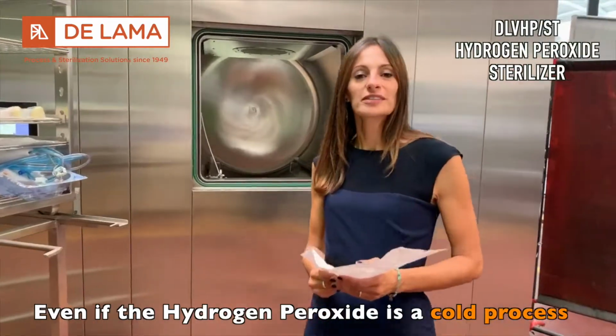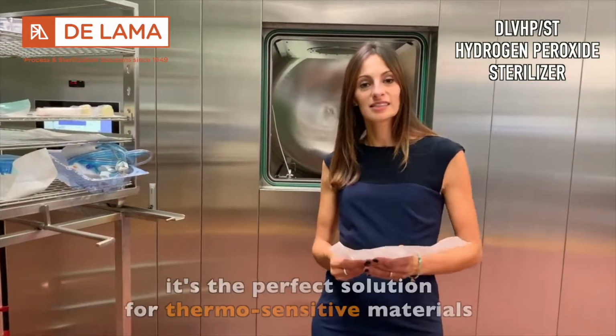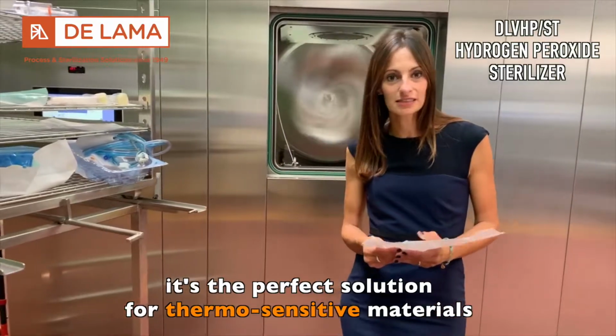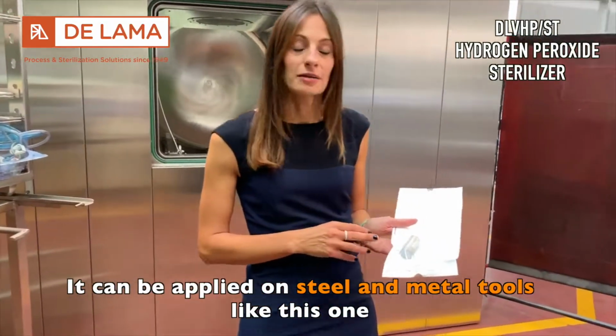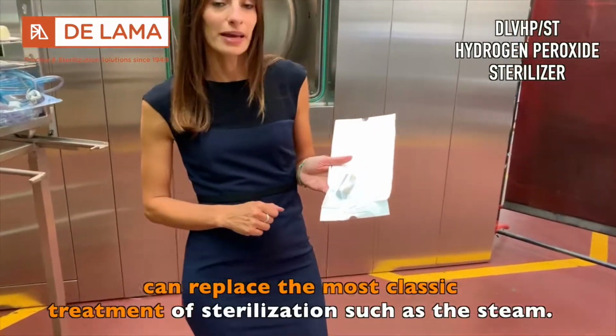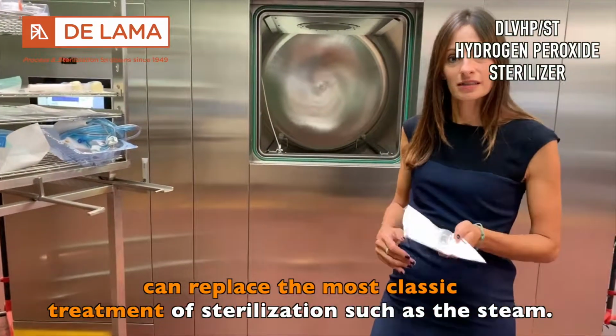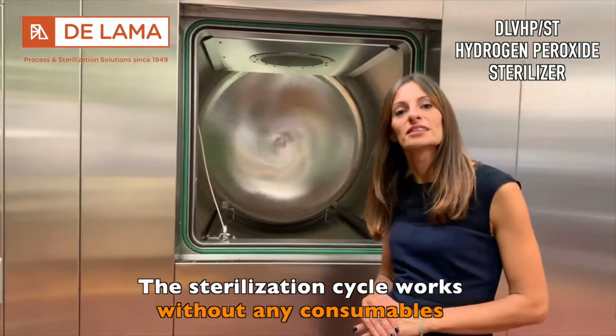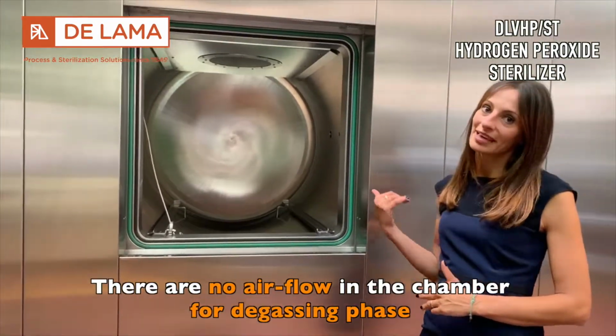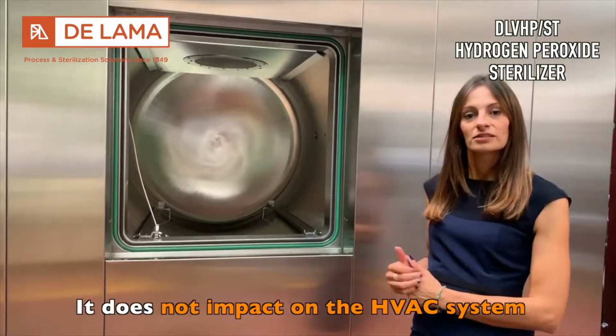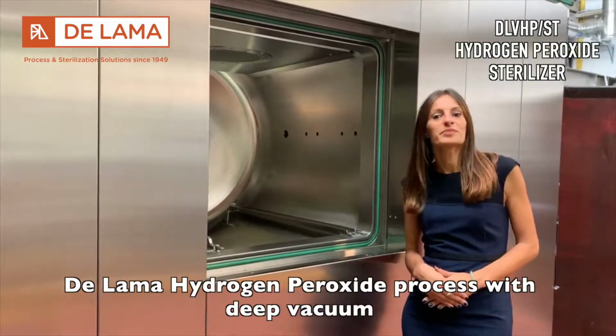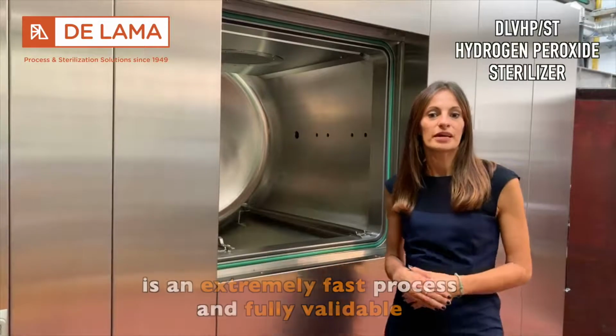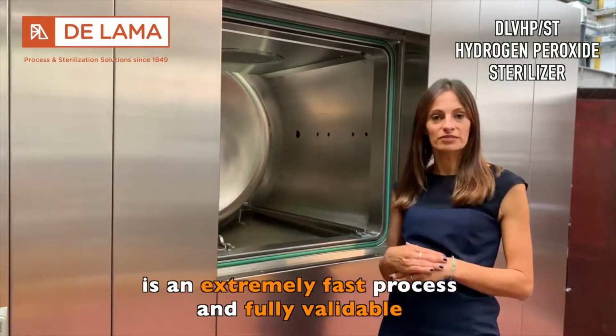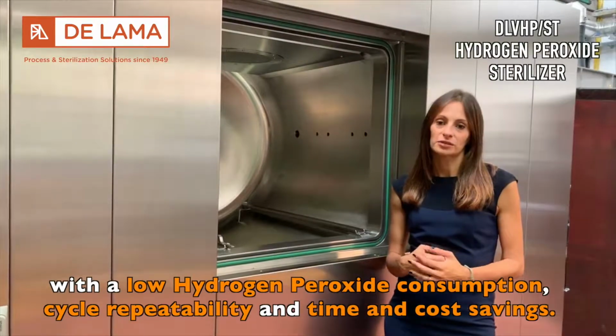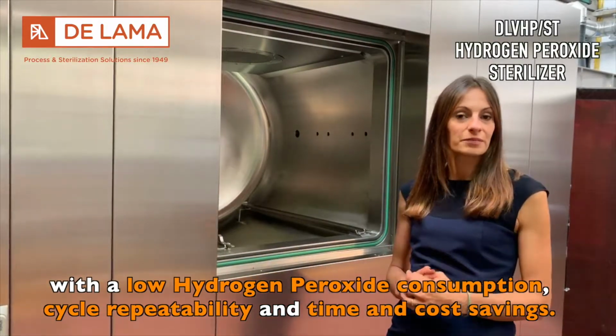Even if the hydrogen peroxide sterilization is a cold process and is the perfect solution for thermosensitive materials, it can be applied on steel and metal tools like this one, and can replace the most classic treatments of sterilization, such as steam. The sterilization cycle works without any consumables. There is no airflow in the chamber for the degassing phase, and it does not impact the HVAC system. De Lama hydrogen peroxide process with the deep vacuum is an extremely fast process and fully validable, with low hydrogen peroxide consumption, cycle repeatability, time and cost saving.